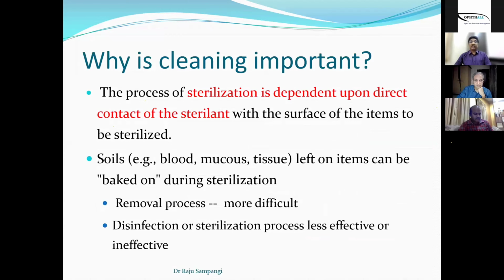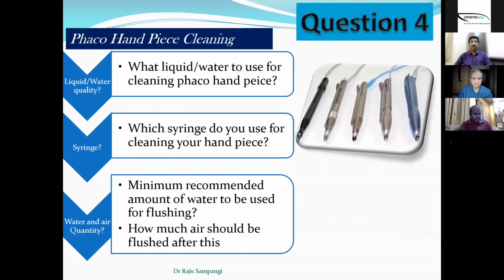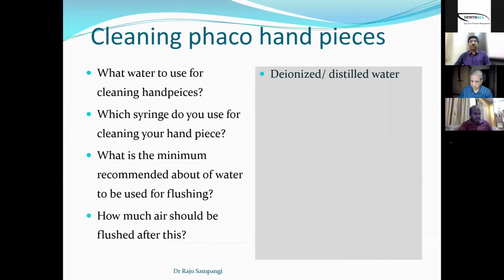The sterilization is important. The cleaning is very important because the sterilization is dependent on the direct contact of the sterilant on the surface of the items to be sterilized. So if you don't clean it properly, then these items will just get baked during the sterilization process. Now, coming to this question, what liquid would you use for your phaco handpiece? The answer is you have to use deionized water or distilled water.